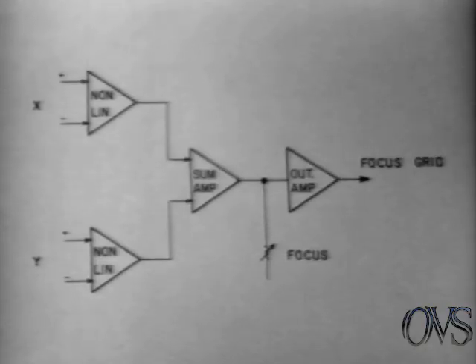The dynamic focus circuitry converts the linear deflection voltages from the X and Y amplifiers into parabolic voltages with non-linear amplifiers. The outputs are summed, combined with a front panel focus signal, amplified, and applied to the CRT focus grid. Similar circuitry is used for dynamic astigmatism control. This concludes our block diagram discussion.